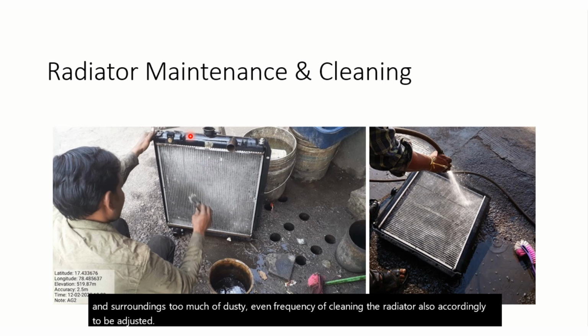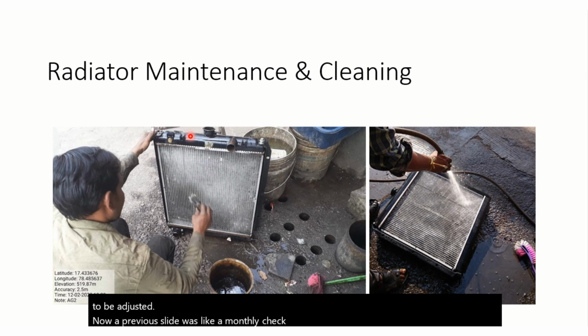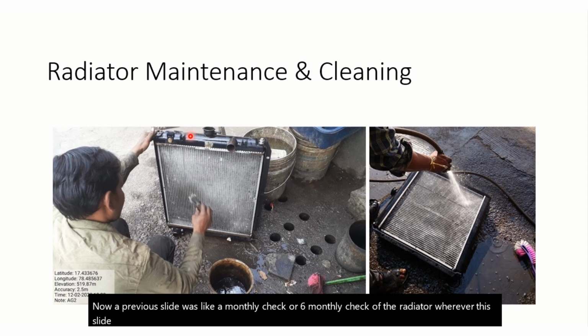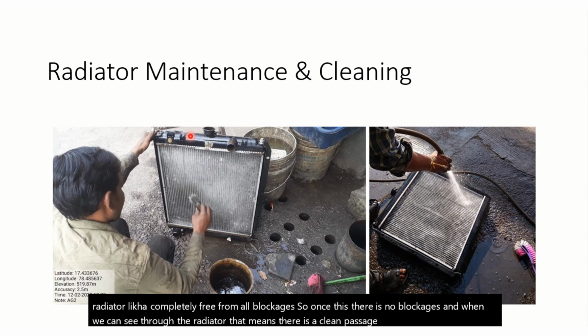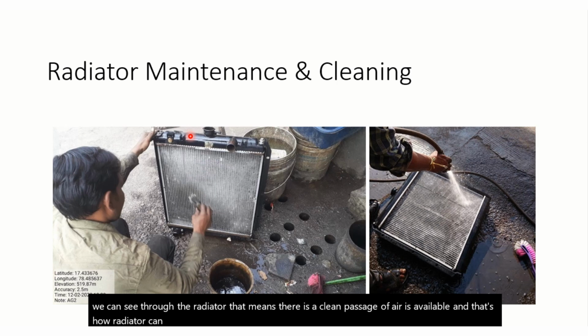Now the previous slide was a monthly or six-monthly check of the radiator, whereas this slide is the C check. Every year the radiator is dismantled from the DG set, and we have to do the force water cleaning so that all the chokes and any damages can be corrected, and we can make the radiator completely free from all blockages. Once there are no blockages, and we can see through the radiator, that means a clean passage of air is available, and that's how the radiator can function properly. So this kind of annual cleaning is mandatory, which is covered in the C check of the maintenance program.